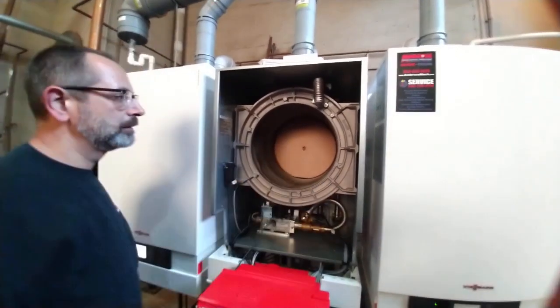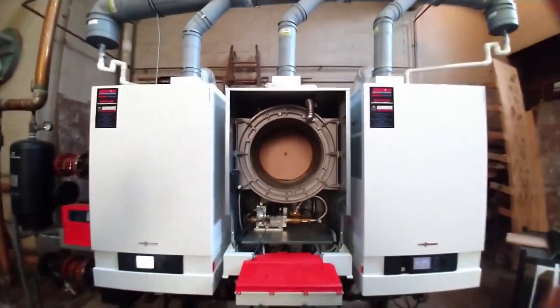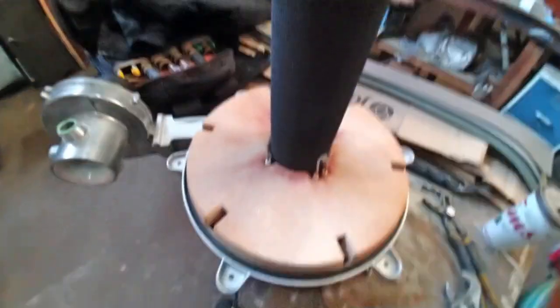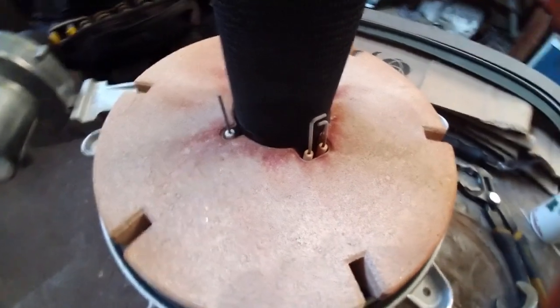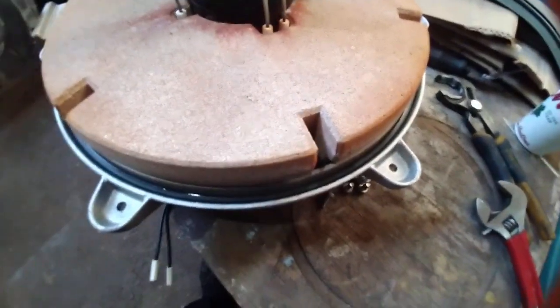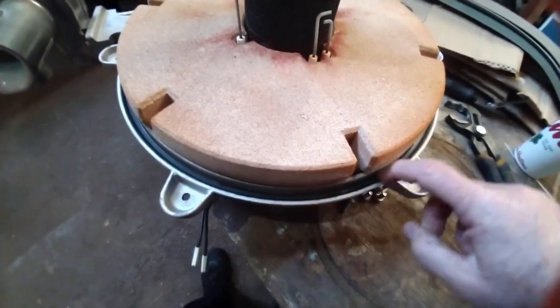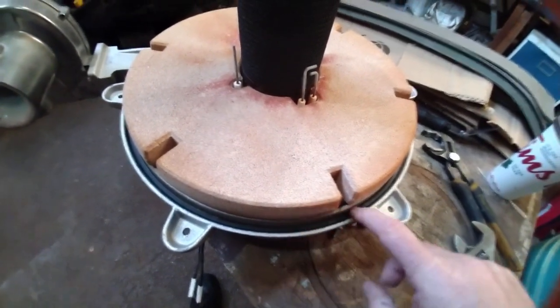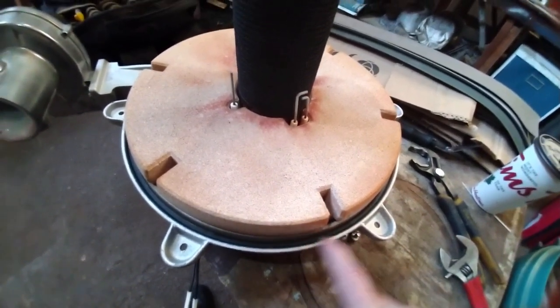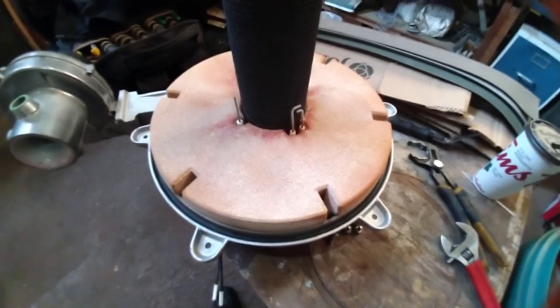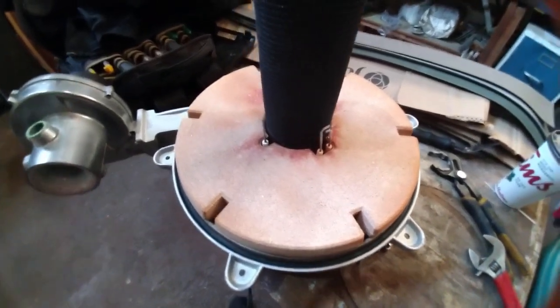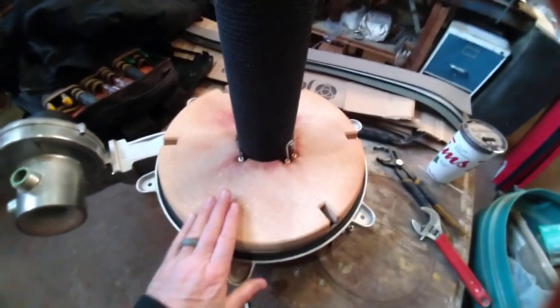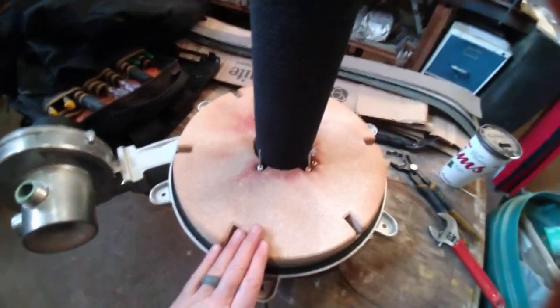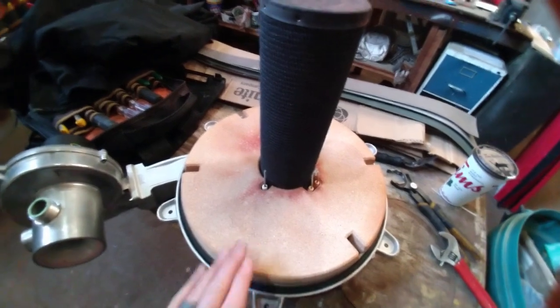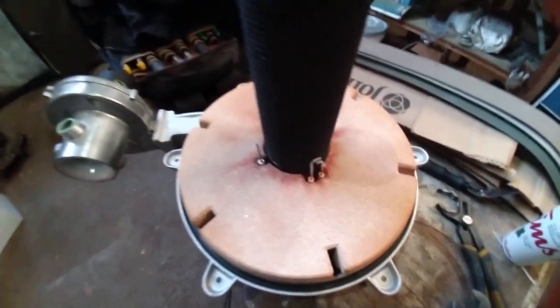Now that we've pulled the front of the heat exchanger plate off, we can inspect the burner. We can actually take a look at the flame rod and igniter from here. We want to inspect the gasket on here to make sure it's going to be okay when we put it back together. They're usually good for a couple of years, and taking them apart and putting them back together a few times. And make sure that the quality of the refractory here is good, that it's not cracked or missing pieces.